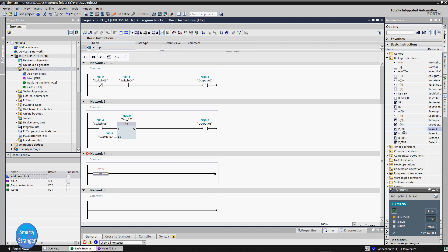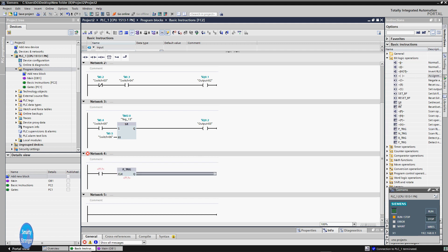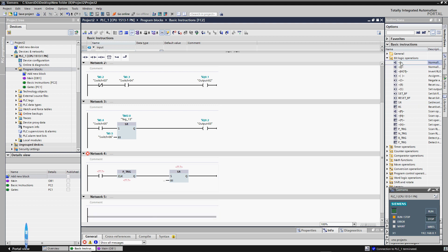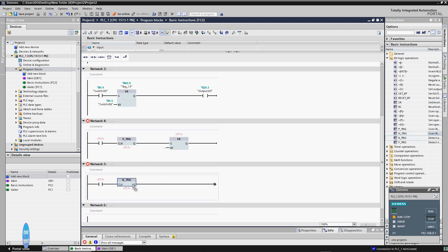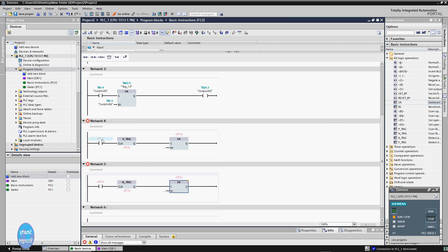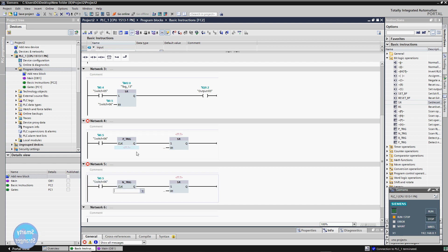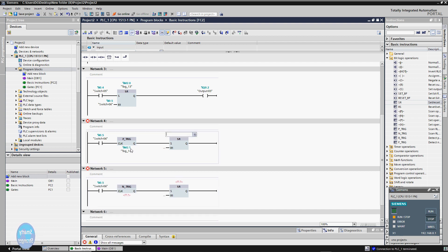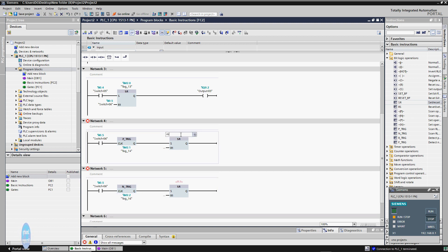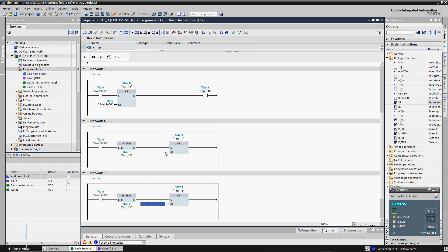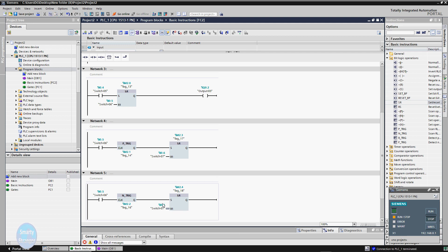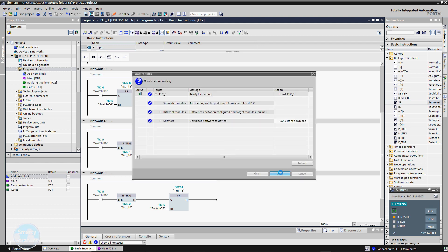Insert a P-transition instruction and an SR flip-flop in one network, and a negative transition instruction and an SR flip-flop in a second network to observe their behavior separately. Attach an input tag to the first normally open contact and define both contacts with the same address by copying and pasting the tag name. Give a memory tag to both transition instructions and attach tags to the reset pins of both flip-flops. Save the program and download it to the simulator, then wait for the download to complete.